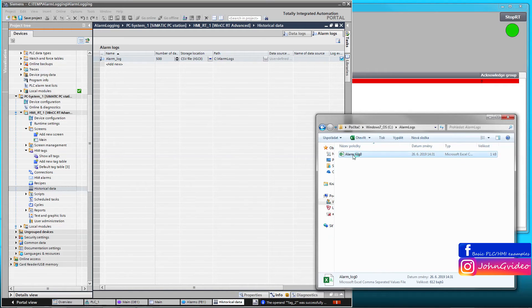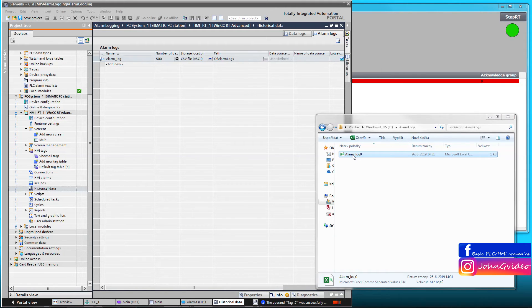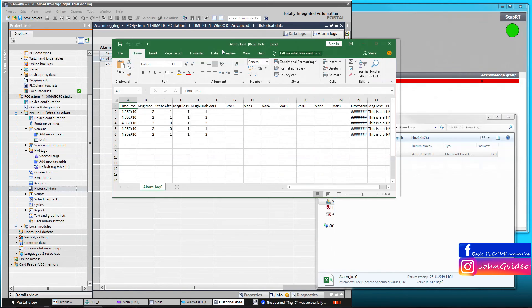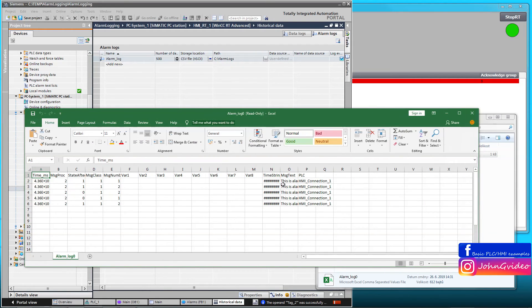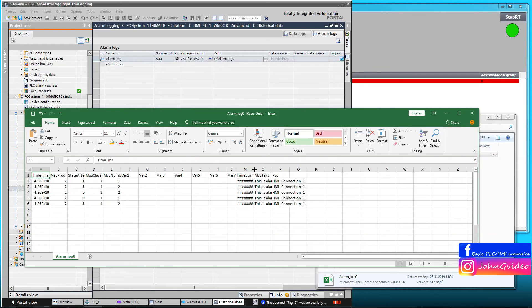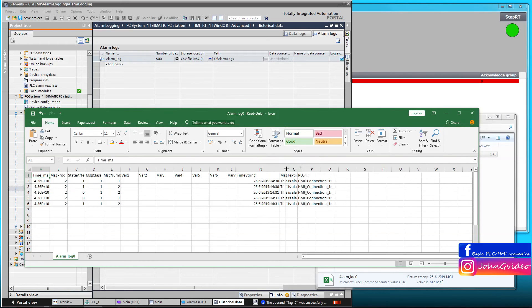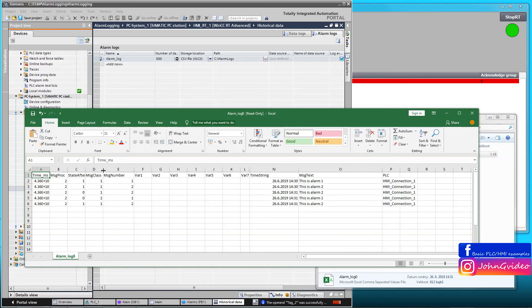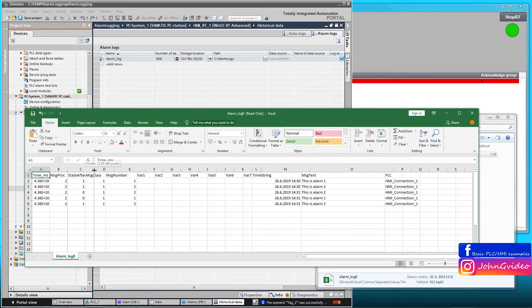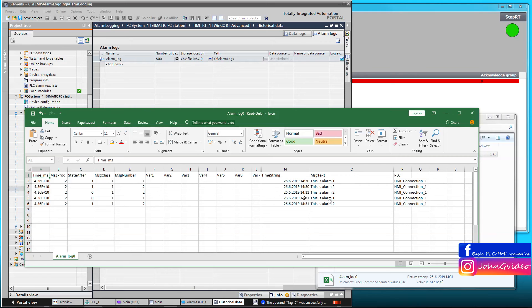Now we can click on the alarm log Excel file and check what is inside. As we can see, the application writes the state of our alarms to this Excel file. We have here: message text, time string, message number, message class and state after, and also PLC connection.